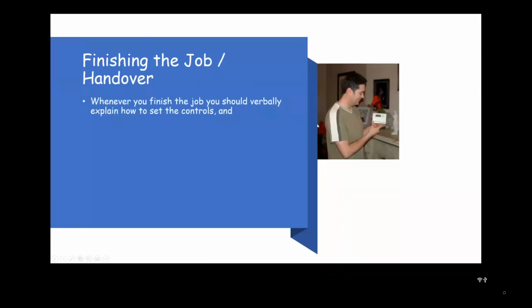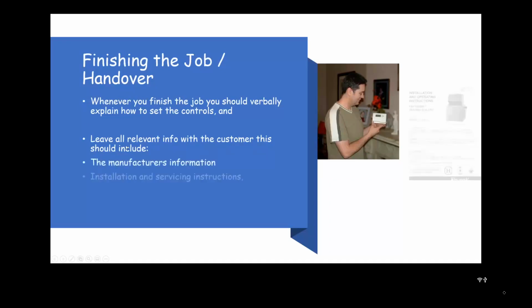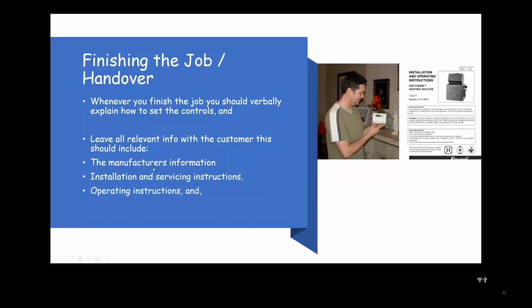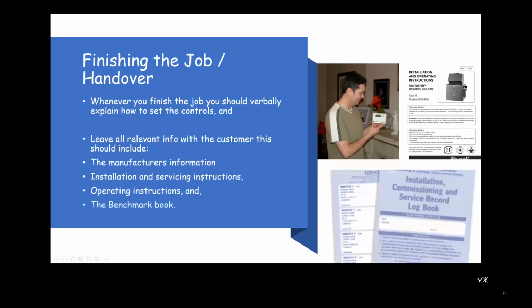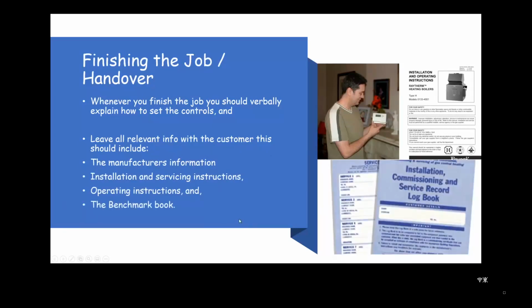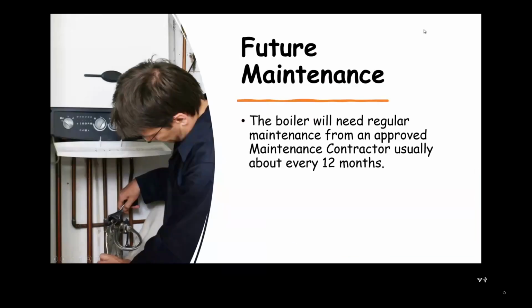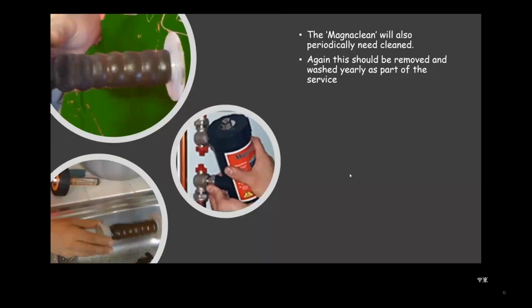Okay, and now finishing the job. Whenever you finish the job and you finish commissioning, you'd verbally explain to the customer how the controls work and how to set them, and make sure you leave all the relevant information with the customer, like the manufacturer's installation, operating and servicing instructions, as well as a completed Benchmark commissioning book. Let them know that the boiler is going to need regular maintenance, normally every 12 months, and that the MagnaClean also will periodically need to be cleaned.